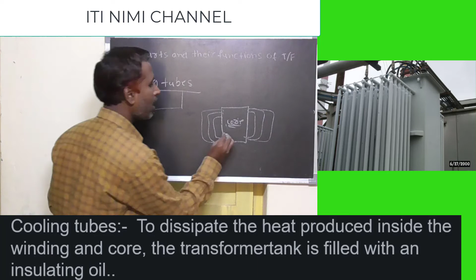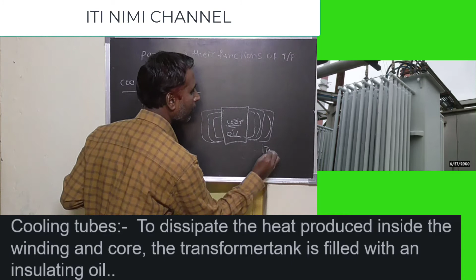The question will come, how does it work? Suppose this is a transformer, and the cooling pipes are fitted outside the transformer like this. When the transformer core is heated, the winding becomes too hot, so the transformer oil carries the heat and comes into these tubes, becomes cool, and again goes inside the transformer core. How is it cooling? Because the tubes are...